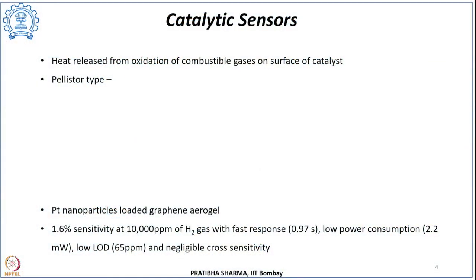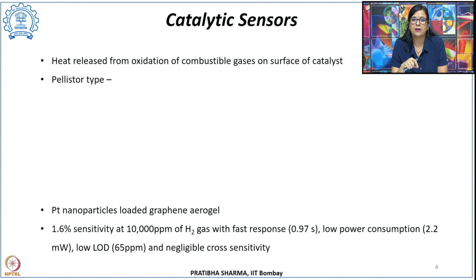Another type is catalytic sensors. These are based on the principle that heat is released due to oxidation of combustible gases on the surface of a catalyst, and that change in property can be used to measure hydrogen gas concentration. Hydrogen is a combustible gas that reacts exothermically with oxidizers, releasing energy of about 142 MJ/kg based on the higher heating value. This release of heat or change in temperature can be used to sense hydrogen gas concentration.